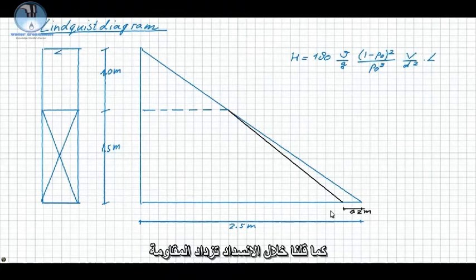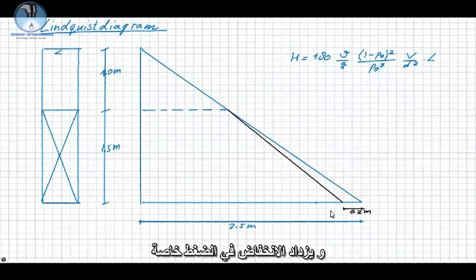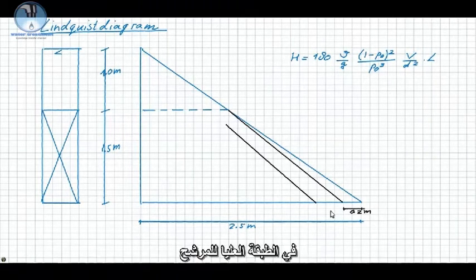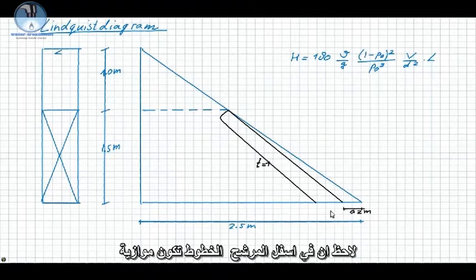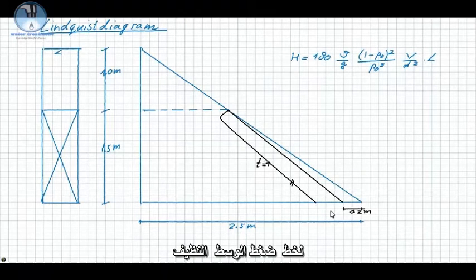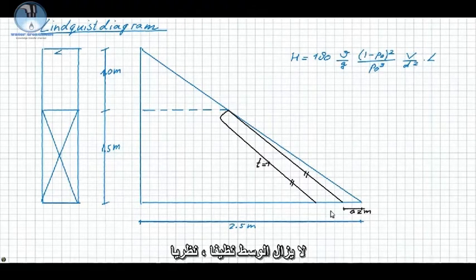During clogging, the resistance increases and the pressure drops further, mainly in the top part of the filter. The pressure line at T=1 can then be represented as follows. Note that at the bottom part of the filter, the line is parallel to the clean bed pressure line, because in that part the filter is still clean.